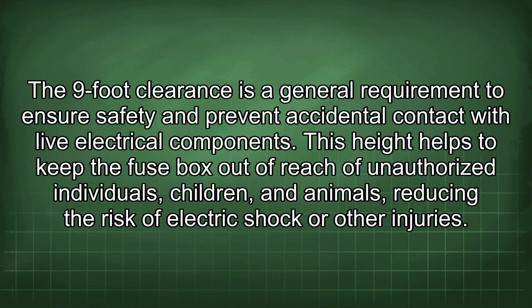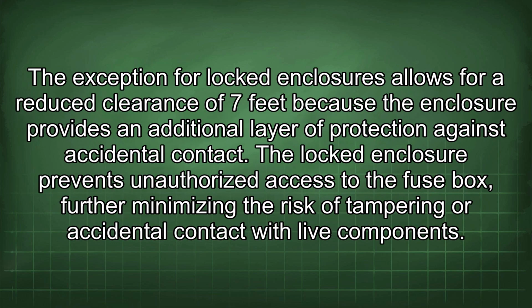The 9-foot clearance is a general requirement to ensure safety and prevent accidental contact with live electrical components. This height helps to keep the fuse box out of reach of unauthorized individuals, children, and animals, reducing the risk of electric shock or other injuries. The exception for locked enclosures allows for a reduced clearance of 7 feet because the enclosure provides an additional layer of protection against accidental contact.